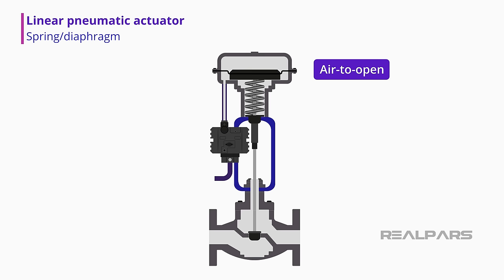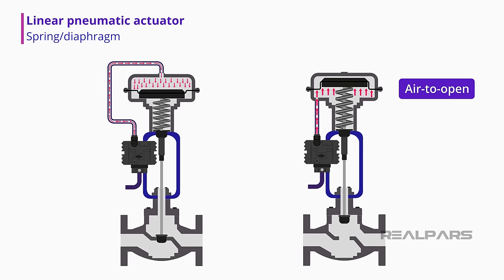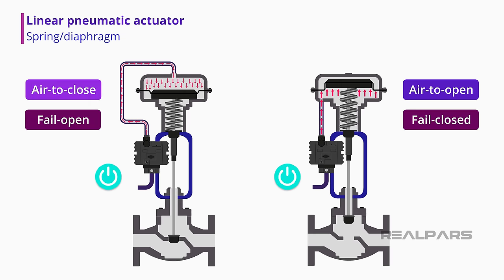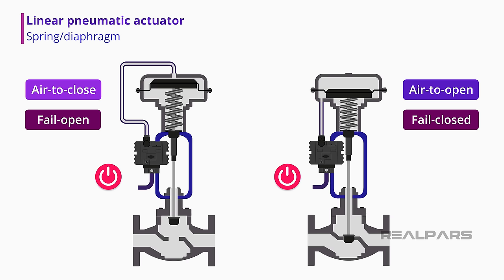In an air to open operating condition, the spring forces the valve closed. The air pressure on the diaphragm creates a force that overcomes the force of the spring and opens the valve. By rearranging the spring and pneumatic supply, this type of actuator can fail open or fail closed when air pressure is lost.